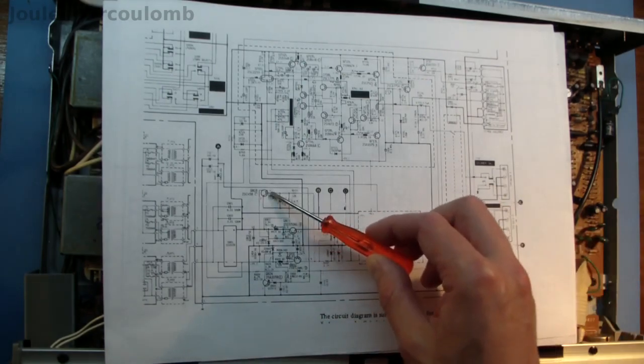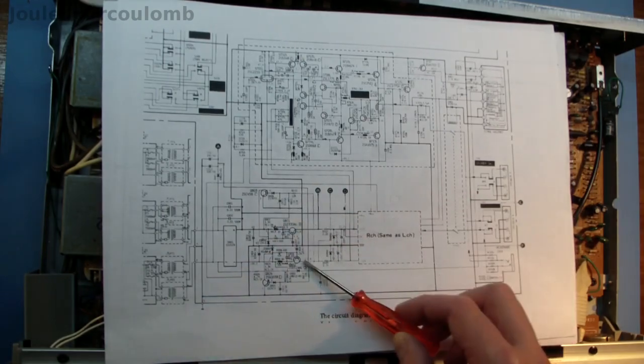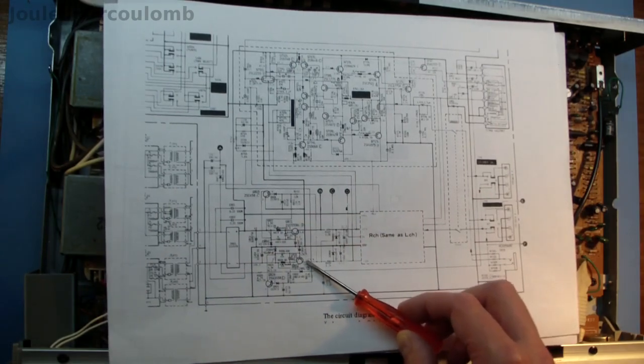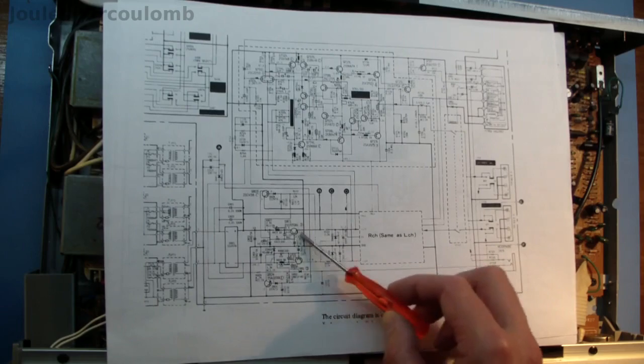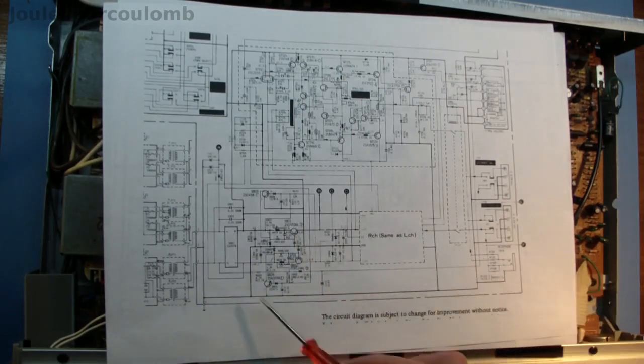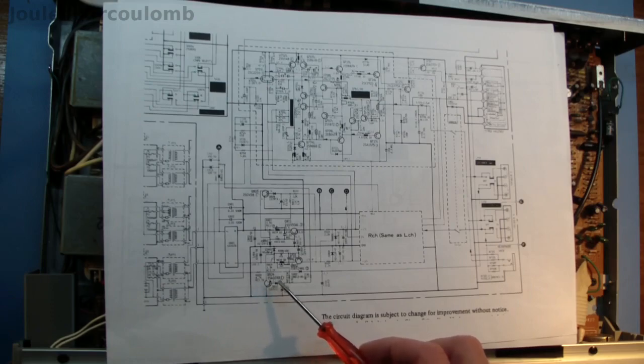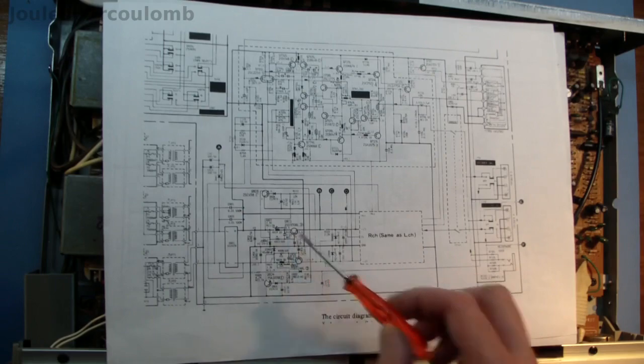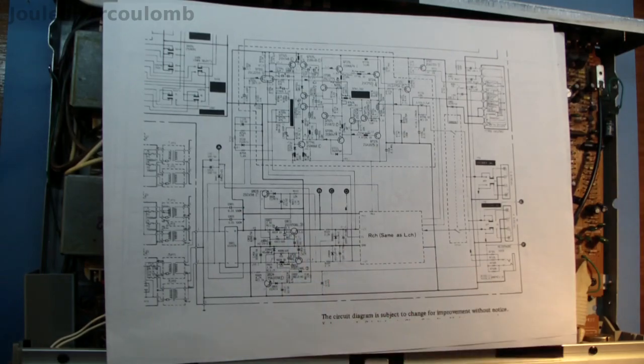This one up here monitors the output of the negative regulator, and if that goes away or becomes too high, then it shuts down the positive regulator. And this transistor here is set up so that if the AC voltage from the mains transformers goes away, then it shuts down the negative regulator. This system should mean that both regulators are shut down rapidly as soon as the mains is turned off and before the reservoir capacitors discharge.